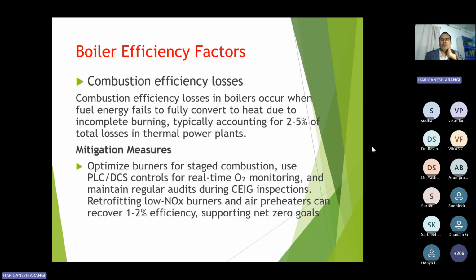Now next, coming to the boiler efficiency factors, mainly combustion efficiency losses. Fuel combustion efficiency losses in a boiler occur when fuel energy fails to fully convert to heat due to incomplete burning, typically accounting for 2 to 5% of total loss in a power plant. So improper fuel burning, improper air flow, and any moisture in the fuel means the fuel will not burn properly. That also will be a loss for the plant. Then mitigation measures: optimizing burners for staged combustion, using the PLC DCS control system for interlocking and logic systems, real-time O2 monitoring, maintaining regular audits, and retrofitting low NOx burners and air preheaters can recover 1 to 2% efficiency, supporting net zero goals.